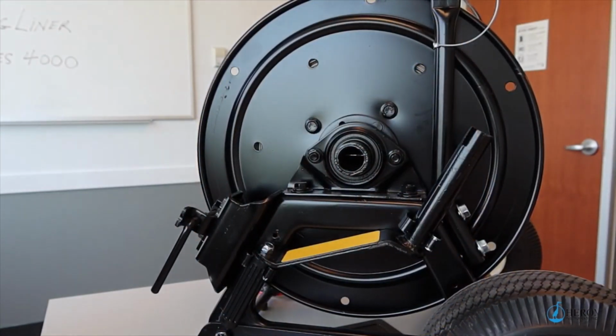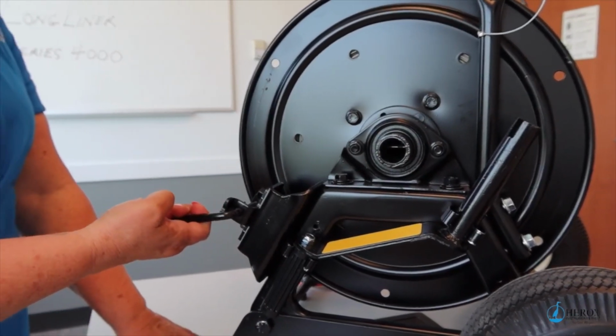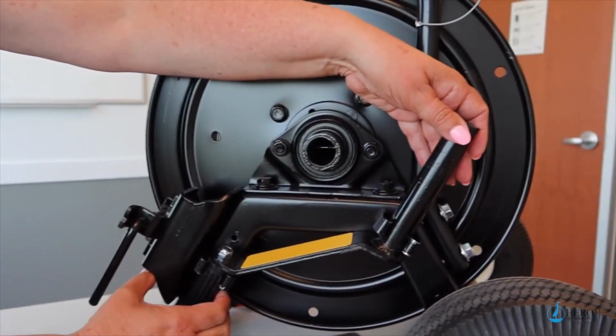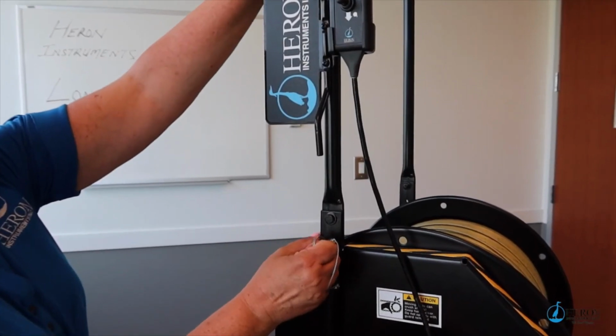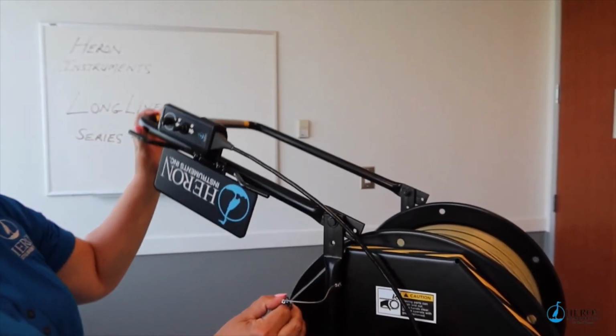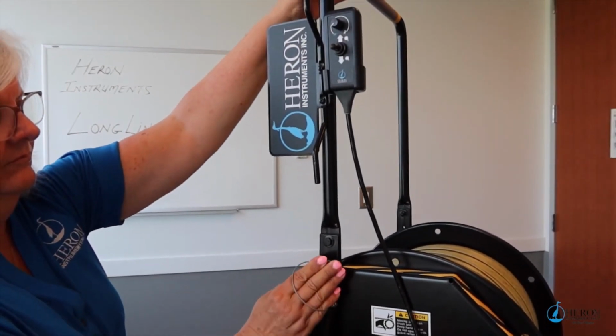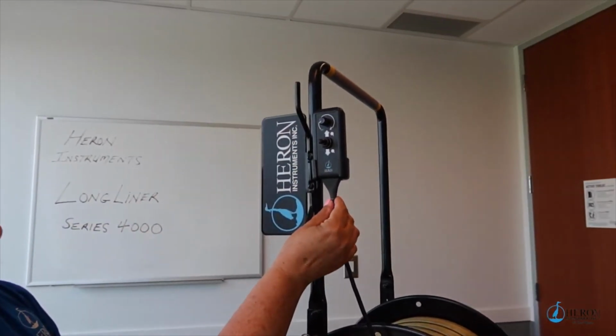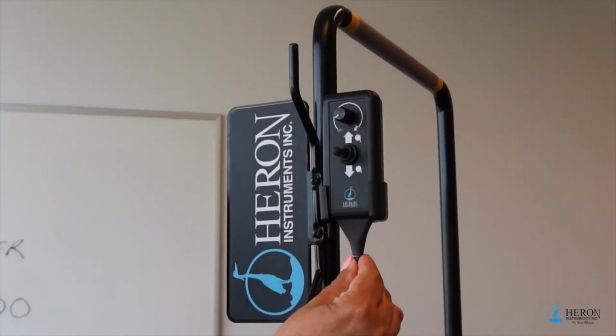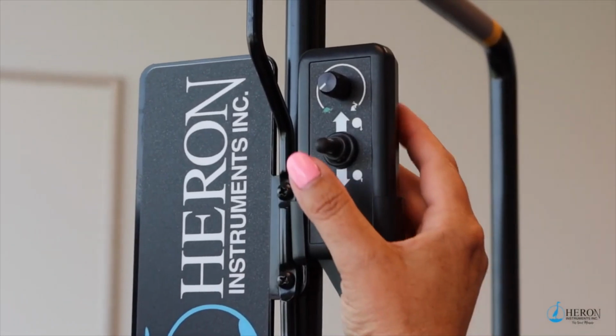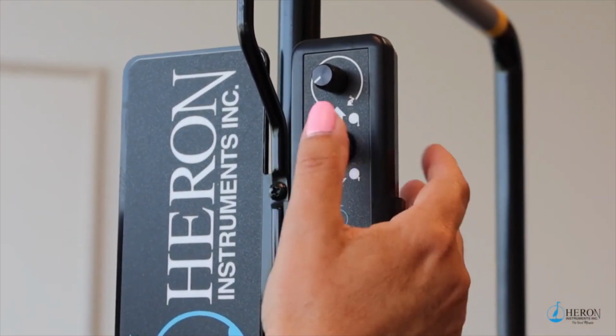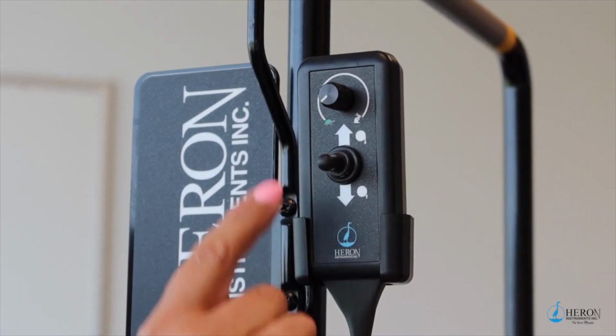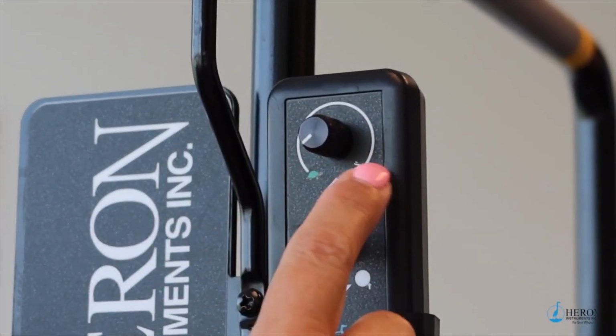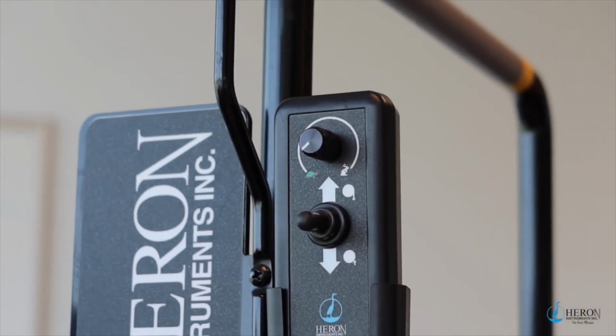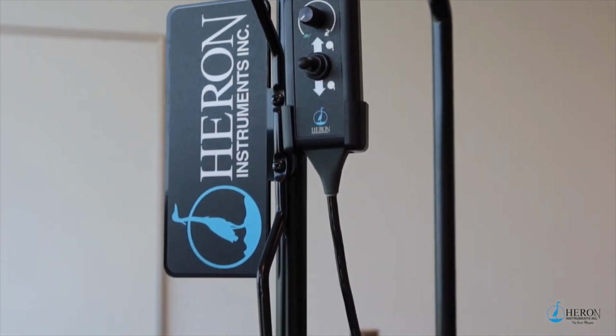On the other side of the reel you will find the reel brake and the fail-safe manual hand crank. The hand crank is ideal to use when there is no power source available. Not only is the cart handle foldable for ease of vehicle transport, but it also provides housing for the cables. The convenient handheld remote is seated in a magnetic saddle. The remote controls the direction and speed of the tape movement. Push the switch up to lower the probe and down to raise the probe. The turtle on the speed control indicates slow and the rabbit indicates faster. The steel hitch port is an ideal way to store the power cable when not in use.